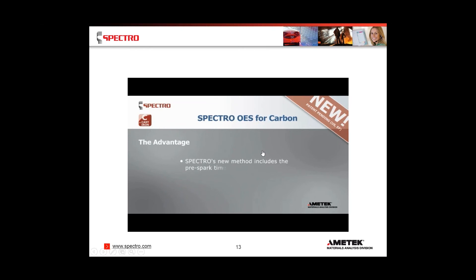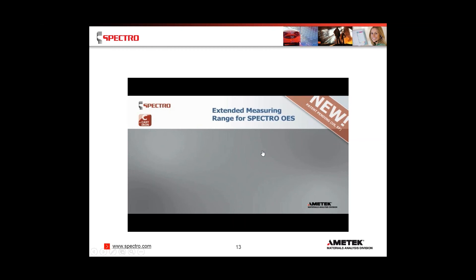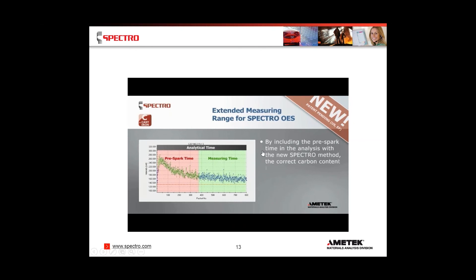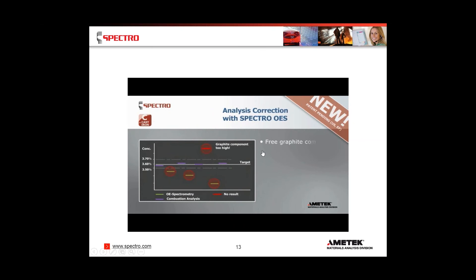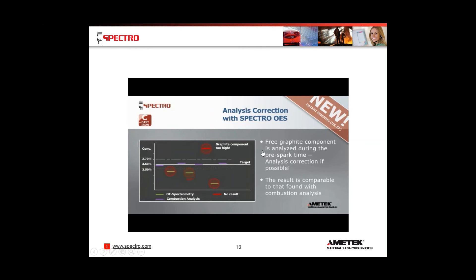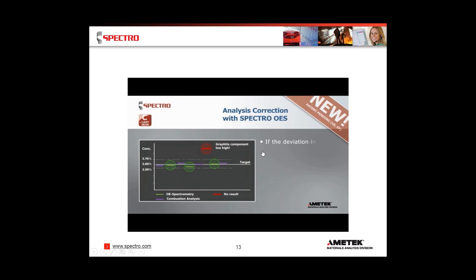The near-perfect way to solve this issue is SPECTRO's advanced method. SPECTRO's advanced method includes the pre-spark time in the analysis of carbon, which also provides evidence as to the quality of the sample itself. By including the pre-spark time, the correct carbon content is calculated and additional information about sample quality is displayed. The free graphite component is analyzed during the pre-spark time, and an analysis correction — if possible — is done, making results comparable to combustion analysis. If the deviation in carbon content is too large, the result is marked as unusable. This method is not designed to completely replace the combustion method, but is expected to eliminate a large portion of combustion analysis work.